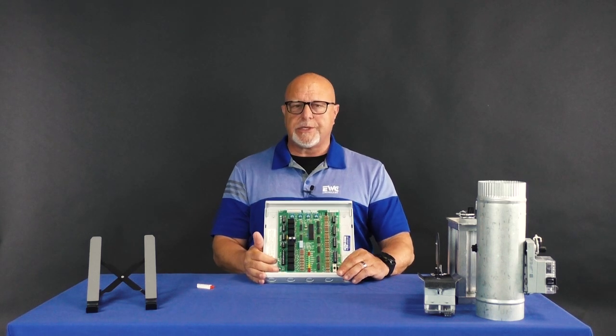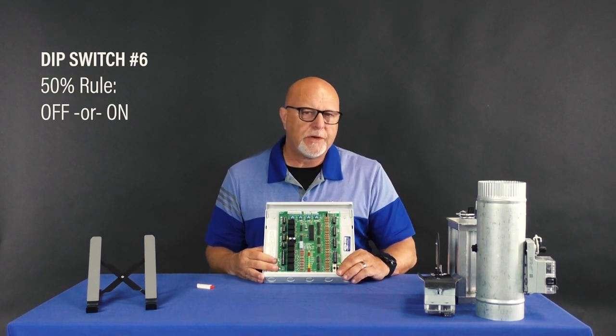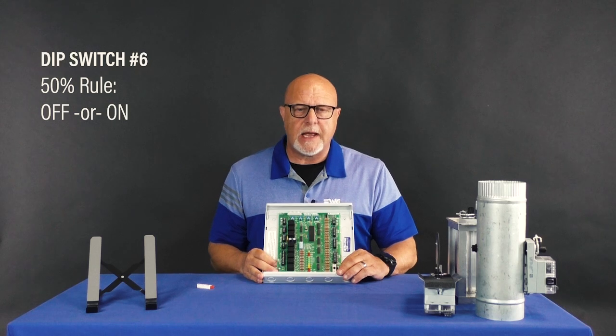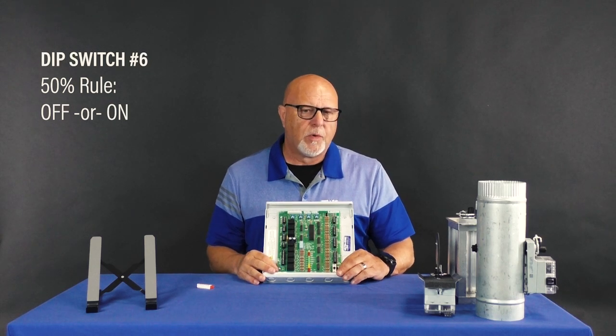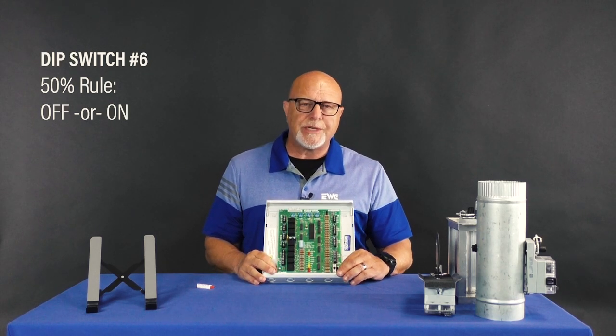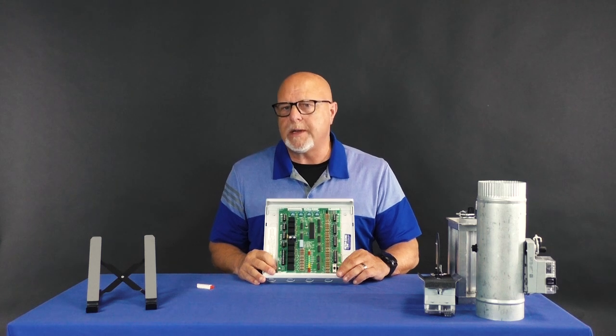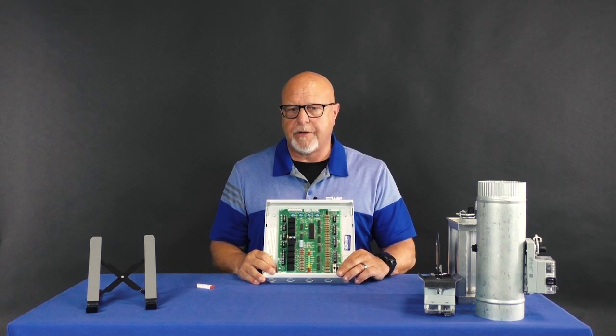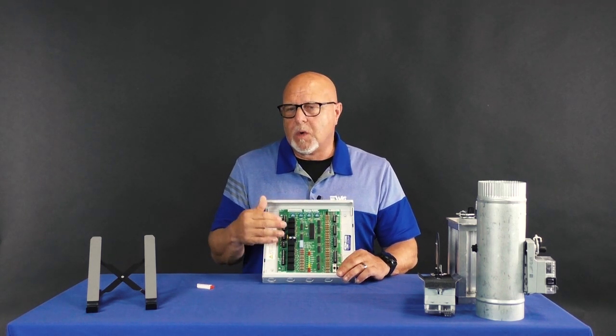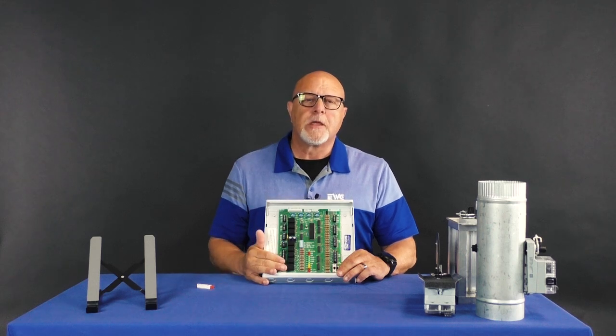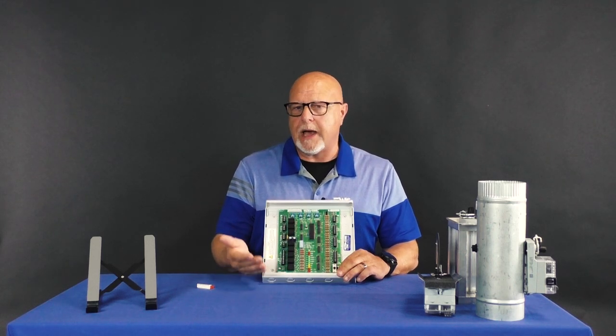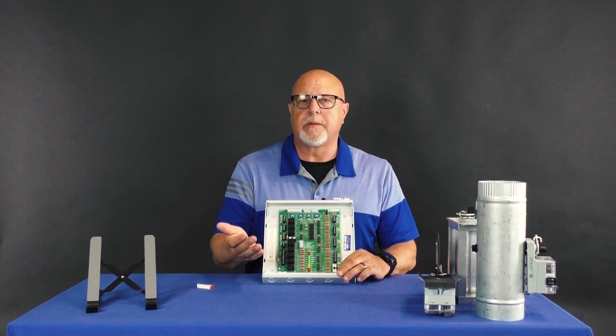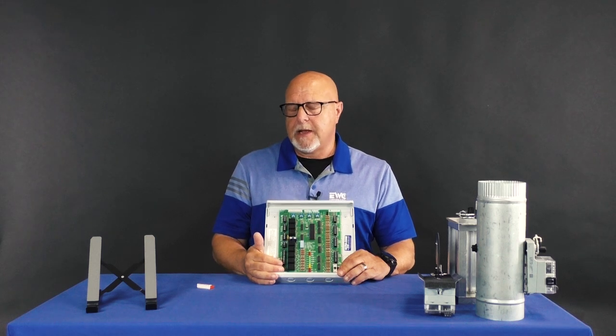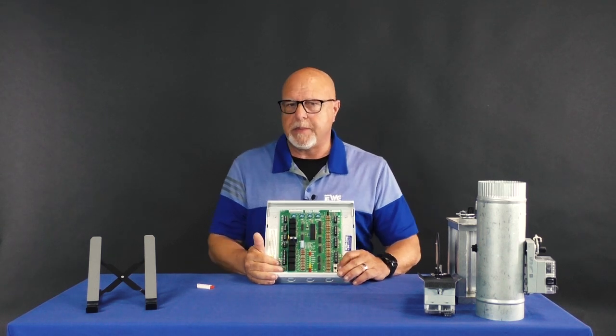The next dip switch option, the 50% rule, is a feature on the board that allows you to restrict the board from going to the higher stage of heating. Meaning, or to better explain it, do you want one zone out of 3 zones to be able to bring on a higher stage of heating? In most cases, the answer to that would be no.